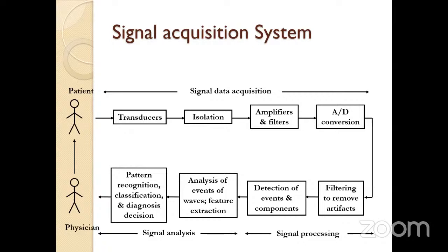The system used to acquire the signal is called a signal acquisition system. Here we have the patient. Then we have the front end of the machine, which has transducers. You might have seen so many wires they connect. For example, in ECG, they connect a few leads to the hand and a few leads to the chest. From the wires, the signal goes to the transducers. Transducers are the ones which convert biosignals or ionic current, whatever we are measuring from human beings, to electrical signals. The transducer converts one form of energy to another form.